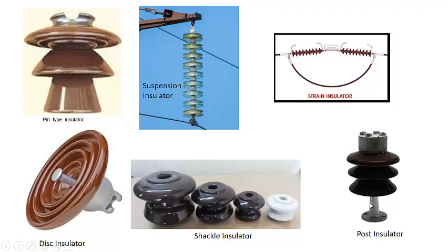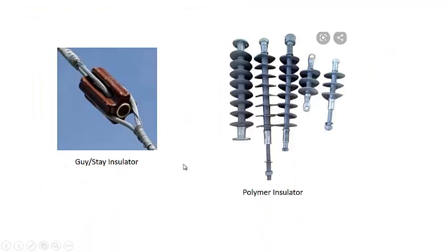This is the post insulator. It is similar to that of the pin insulator. Only thing is that we have some sort of connection at its top and bottom so that we can extend or connect other post insulators over this to be used in higher voltage levels. Now this is the guy or stay insulator. It can be connected like this for the upper part of the wire and for the lower part of the wire, so as to isolate the upper part from the lower part. It is used in the tie wires to support the poles.